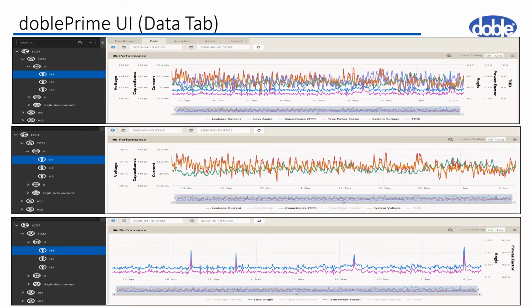This slide is showing 3 separate screenshots from the data tab. And the data tab is a graphical view of one monitor, one channel for a specific period of time, in this case, 2 months. In this case, we're viewing the data associated with the H1 bushing monitor. When this chart's first viewed, it can be somewhat confusing because there are a lot of squiggles in it. However, any of the channels can be turned off by clicking on the channel name on the bottom of the chart, or by clicking on the ghosted channels, you can turn them back on.